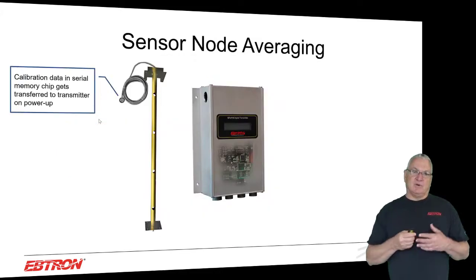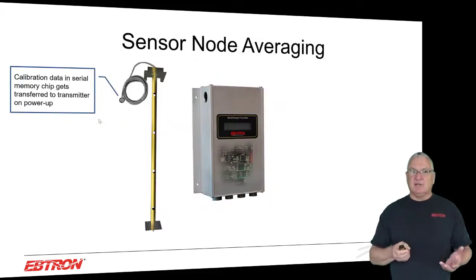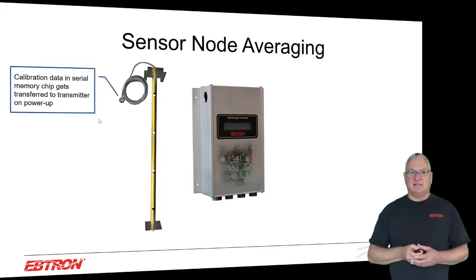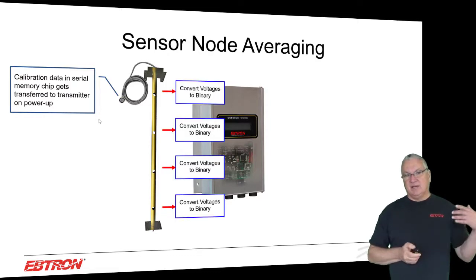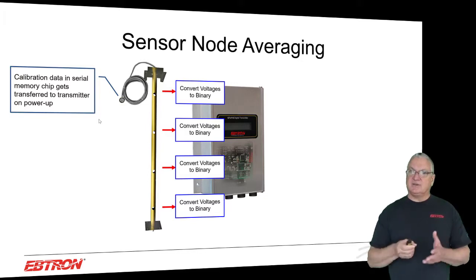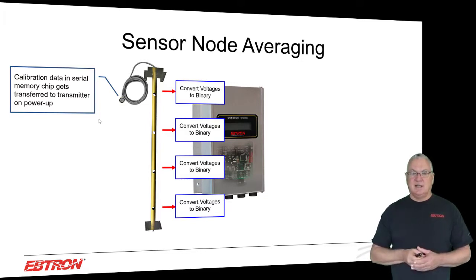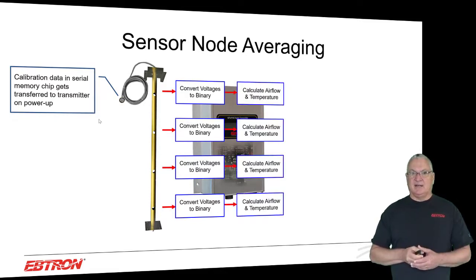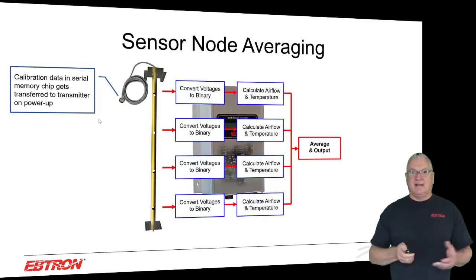When you look at what we're doing in the field, it's really a reversal of the calibration process. Each one of these probes, if you look closely, you'll see that each sensor node is barcoded and serialized, and that data gets written to a one-wire memory chip in the connector. When you plug it into the transmitter, all that calibration data goes over, and all the transmitter is doing is reversing the calibration process. It converts the voltages to binary, and then we calculate the airflow and temperature of each point, and then average and output. It's very simple, but very independent.